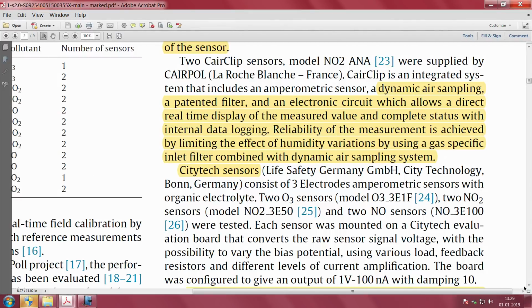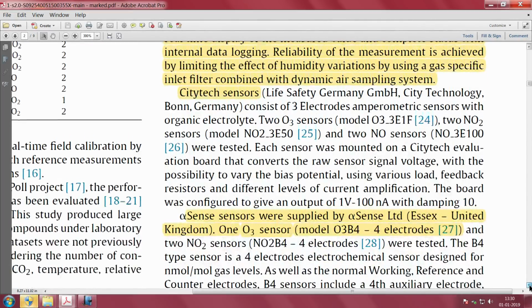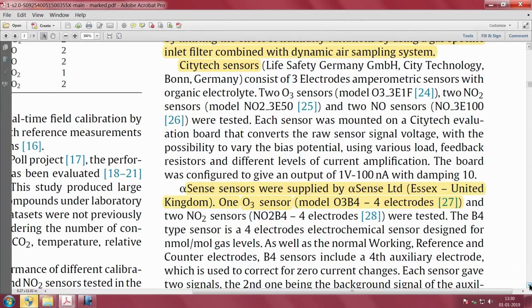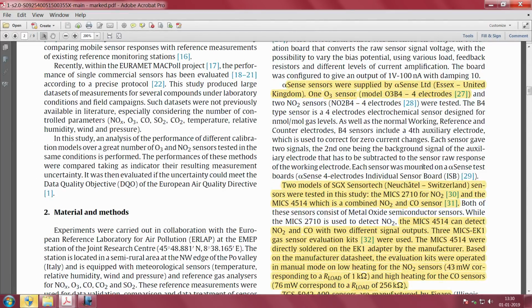Another thing that can bring down the reliability of measurement is the effect of humidity variations. Using a gas specific inlet filter combined with a dynamic air sampling system, these smart electronic systems remove humidity and improve not only the lifetime of the sensor but also the reliability of measurement. Alpha Sensors is another company, quite popular for IoT applications, and then of course SGX Sensor Tech, which we will go into in a little detail.